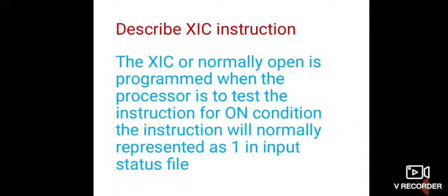Then XIC, examine if closed. This XIC instruction, or normally open instruction, is programmed when the processor is to test the instruction for on condition of the input. That is, if the input is on, the XIC instruction is true, otherwise it is false. The XIC instruction is the opposite of the XIO instruction.